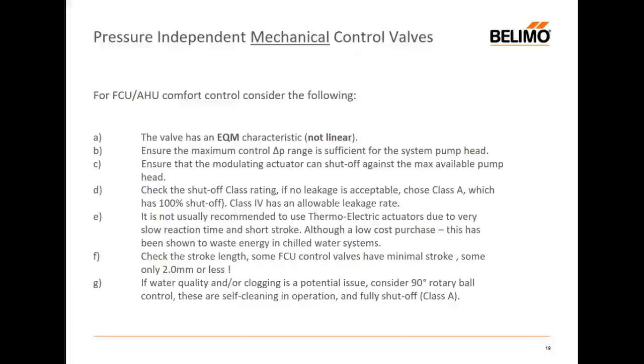So for pressure independent control valves, I don't think it's sufficient to say I'm going to specify a pressure independent control valve, all my troubles will be over. I think there are many, many manufacturers out there, some good, some not as good as others, and different styles, different types, different materials. But these are some questions I thought are interesting to consider when you're selecting PI valves. The first and foremost is, because I'm modulating with PI valves, I need to have an EQM characteristic. This is an absolute must. I should not have linear if I expect to modulate.